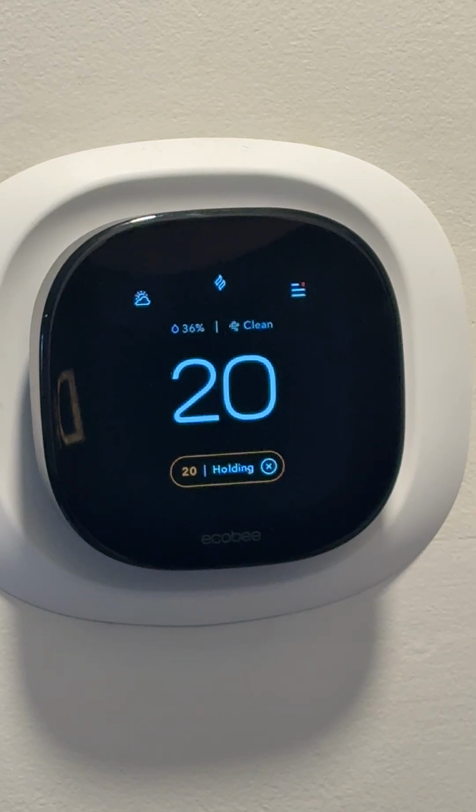You can even think whenever we have warm weather, usually that means there's snow coming. So we have a warm day, there's a bunch of snow. We'll never damage our heat pump because it does a trial spin. It ensures that there's no ice or snow in the fan. If it hits any of that snow or ice, it's just going to lock out. And we're going to get some weird fluctuations, error codes and stuff on the thermostat telling us the heat pump's not working properly. But we don't really want that.